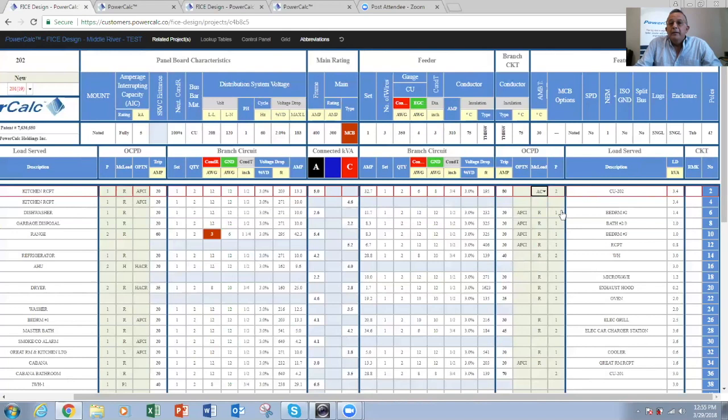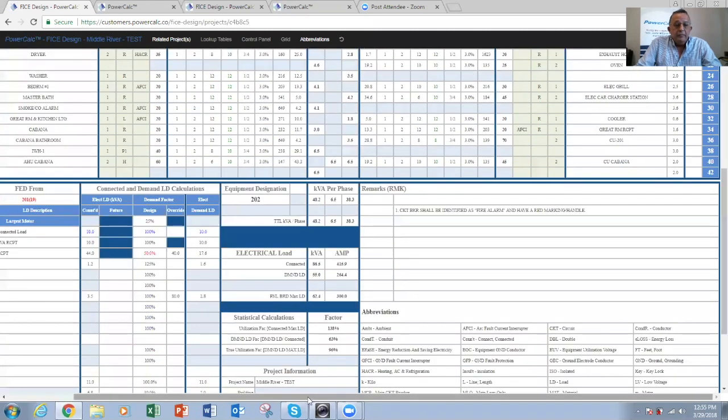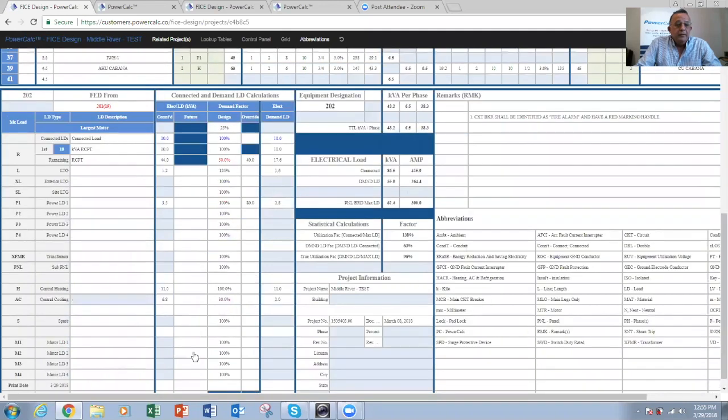calculate. Well, I kept the same value. I guess it's within the same parameter, okay? And then down here, it included central heating 11, cooling is 6.8. It took the largest of the two at 100% and the smallest at 30%. Again, I put that as a default because during the heating cycle, the blower fan is being used, and I estimated it to be about 30%.